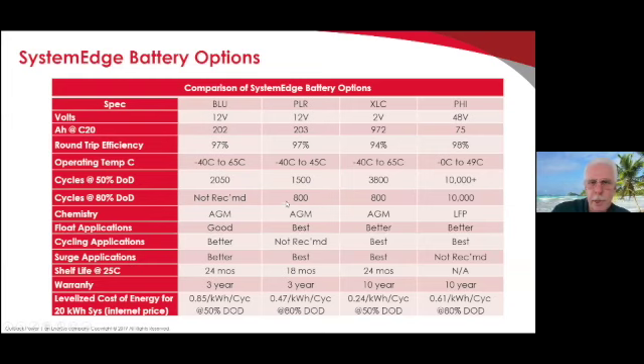80% depth of discharge, that's not recommended for the Blues. They really don't like to be discharged more than 50%. You can see that the PLRs drop from 1500 to 800 cycles when you go from 50 to 80% depth of discharge.